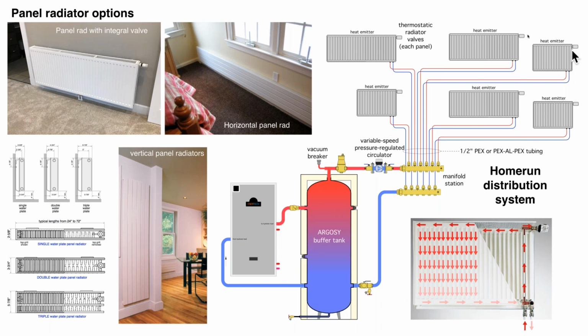And each radiator has a thermostatic valve, no batteries, no wires. That valve automatically responds to changes in room temperature, and it adjusts the flow rate going through the panel to maintain that room temperature. And it's a simple, very repeatable concept. I'm showing 6 radiators. It could be 8, it could be a dozen, it could be 4. Very scalable. These panel rads are available in different thicknesses and different heights, different lengths. And you can go to the manufacturers and get the data on performance.